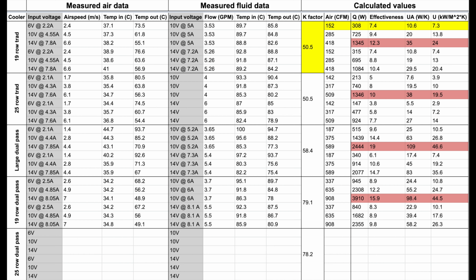So the K-factor doesn't change. The K-factor was strictly based off of the physical measurements, so that's going to be the same for all of these. It's just 50.5. So 50.5% of the frontal area of this heat exchanger is airflow. The CFM approximated from this data, the 2.4 and the rest of the data here, is approximately 152 CFM. So with all that data, we end up seeing that it was pulling 308 watts. The effectiveness value came out to 7.4%. The UA was 10.6, and the U value was 7.3.